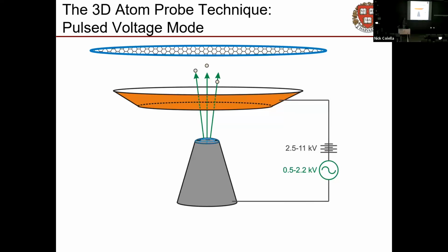In this case, a few thousand volts is enough. So we put a few thousand volts on your pointy little tip with a counter electrode nearby, and we turn it up until your tip almost comes to pieces. We don't want it to just all explode at once, though, because remember, one of the important things about time of flight is we've got to have that stopwatch, which means we've got to tell it when to explode.